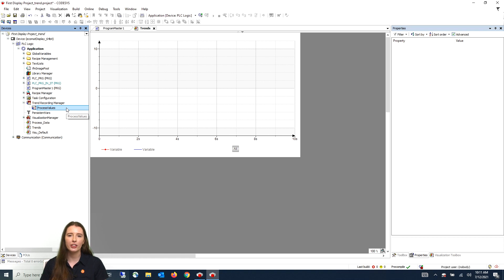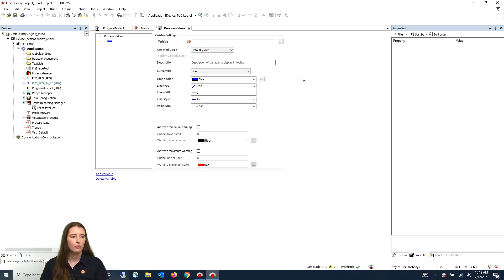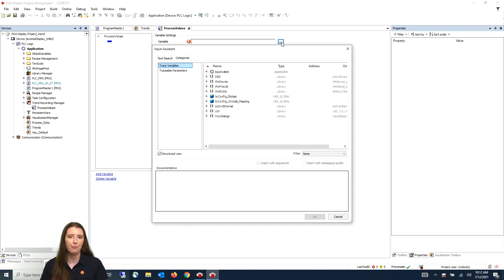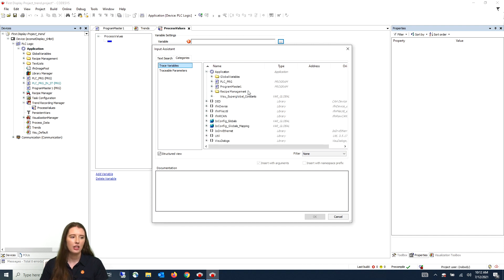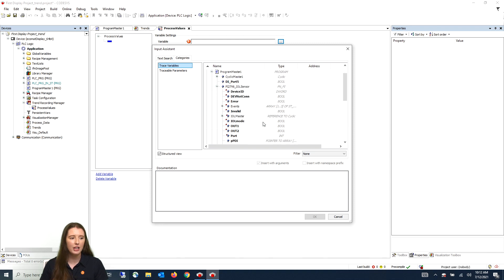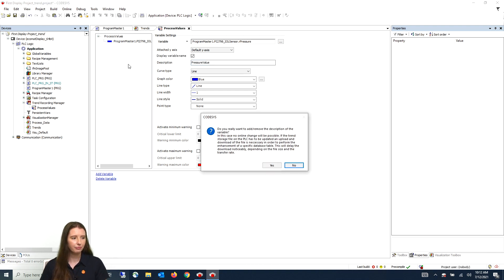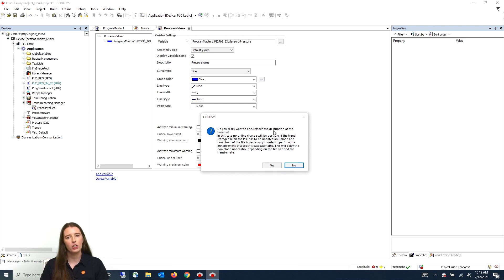For our example we want to trend the real pressure and temperature process values. To do this you need to add the values to your trend recording. We will do this by opening our process values trend window and clicking on add variables. Select the three dots to the right of the variable window and navigate to your program by expanding application. My program name is program master 1, then go to the function block of the process value you want — I'll go to the PI 2798 function block and navigate to the R pressure value. In the description give this a name, select enter, and a pop-up box will appear — select yes.